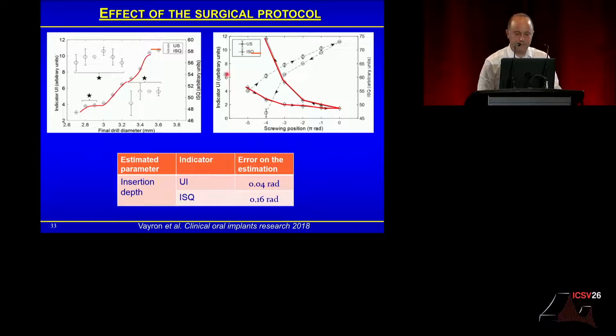And eventually, when you screw an implant, you go from here with ultrasound to here. You increase the stability, so you decrease the ultrasonic indicator. That's logical. And then when you unscrew it, you go in the other direction and you increase the ultrasonic indicator. That's logical. You get pretty much the same results for the resonance frequency analysis. And again, we could derive an error on the estimation of the insertion depth that is lower using ultrasound than ISQ.